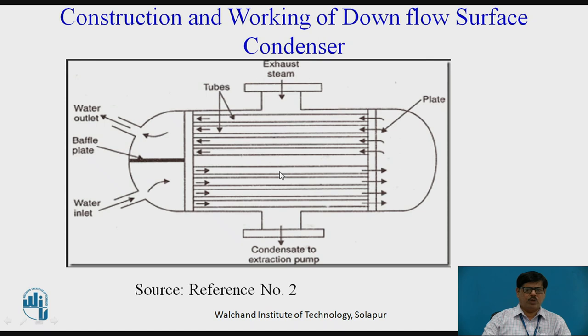When this steam enters into the condenser shell, it comes in contact with the cold surface of the tubes because the cooling water is circulated through these tubes. The cooling water is circulated with the help of a cooling water pump through the lower half portion of the condenser shell. It flows from one end to another end and then enters into the upper half portion of the condenser shell where it returns back and goes out. When the exhaust steam comes into contact with the cold surface of the cooling water tubes, it gets condensed and the condensate is removed from the bottom side with the help of a condenser extraction pump. This surface condenser is very commonly used in modern steam power plants because the vacuum produced inside is of high level.